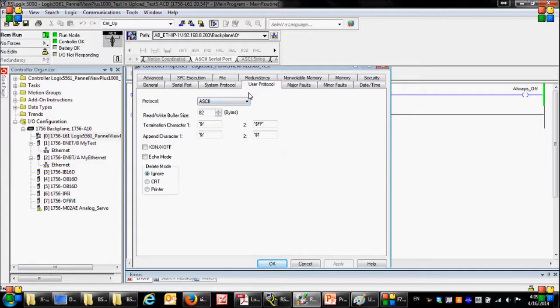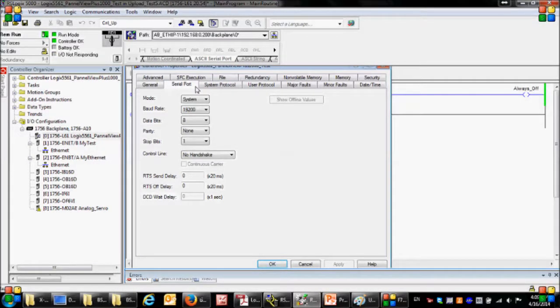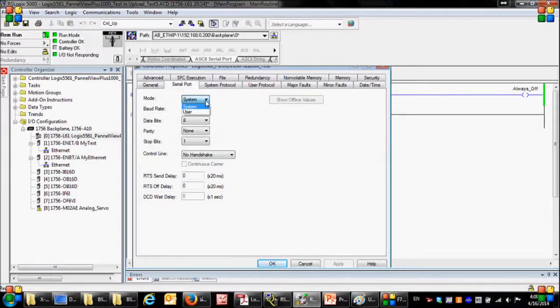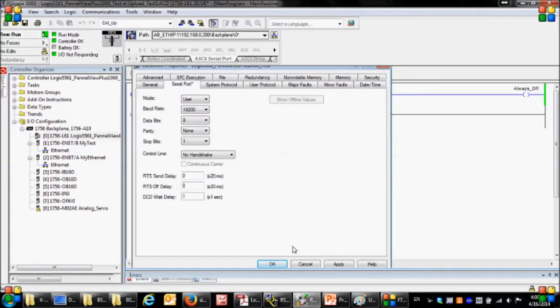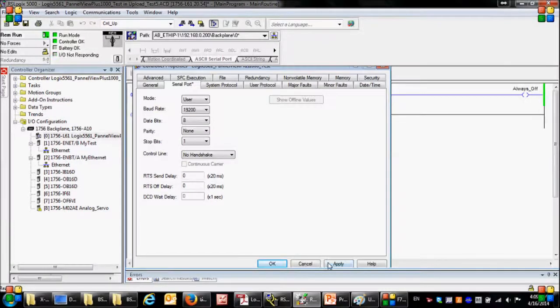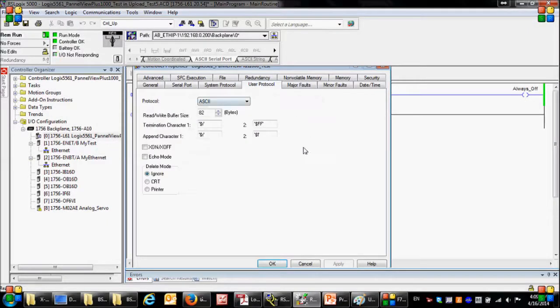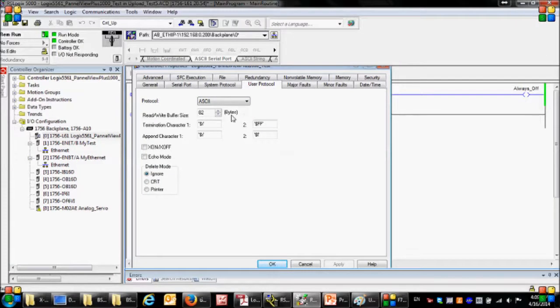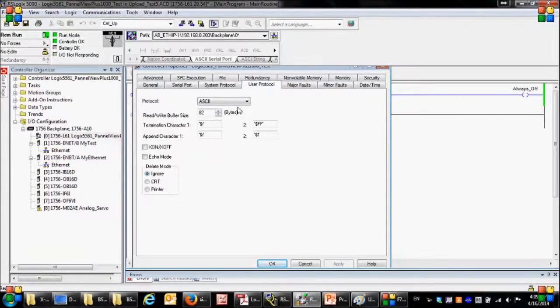Here among all these tabs I just need to check the serial port tab and the user protocol tab. In the serial port tab, first I need to change the mode from system to user so that I can take the control of the serial port. For the rest of the settings I am going to keep them as they are, then apply. Then in the user protocol tab you can see other settings, for example the buffer size which indicates the size of the buffer that stores the sent and received data.